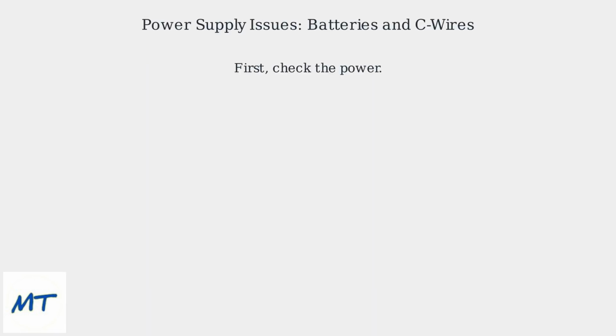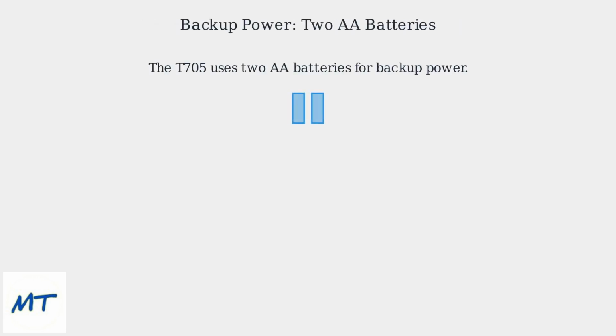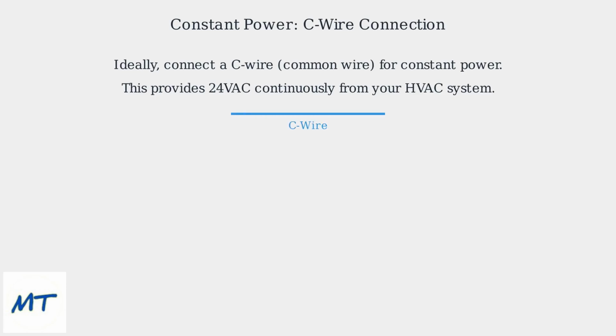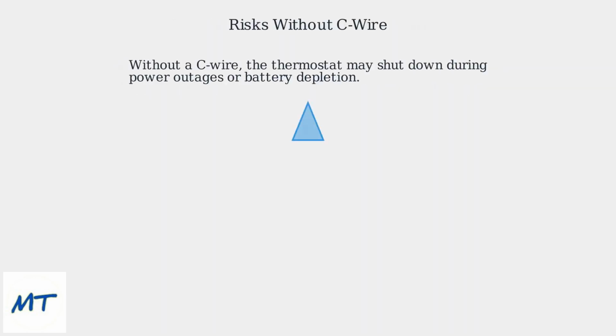First, check the power. The Pro1 T705 thermostat requires reliable power to function correctly. The thermostat uses two AA batteries as backup power. These provide temporary power during outages or when the main power is insufficient. Ideally, the thermostat needs a C wire or common wire connected for constant power. This wire provides 24 volts AC continuously from your heating and cooling system. Without the C wire connected, the thermostat relies solely on batteries. This can cause it to shut down unexpectedly during power outages or when batteries run low.